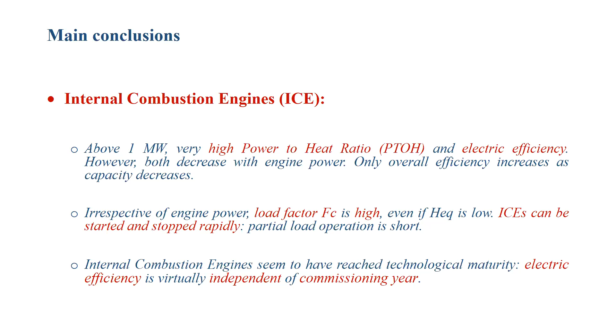The load factor is always high, irrespective of the power we're talking about, and it is high even if the equivalent operating hours are few. This means these engines can be started and stopped rapidly, so they're very flexible and very good where a high number of starts and stops is needed; they're suitable for this. Finally, they have reached their technical maturity, because there was no significant increase in electric efficiency from 2011 to 2019.